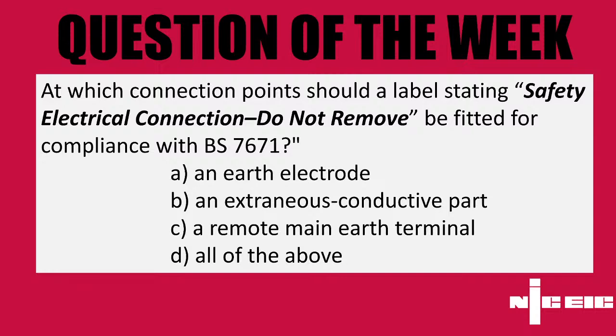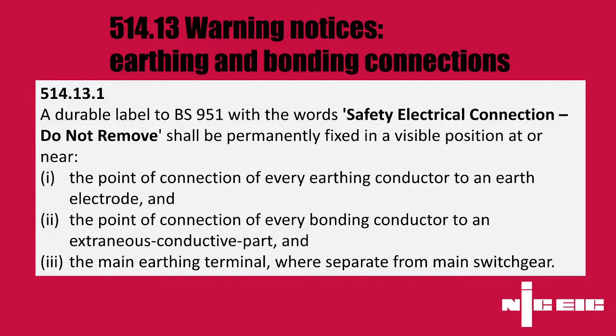If we actually go to that area of BS 7671, we'll see regulation 514.13.1, and that clearly states a durable label to BS 951 with the words "safety electrical connection, do not remove" shall be permanently fixed in a visible position at or near the point of connection of every earthing conductor to an earth electrode, the point of connection of every bonding conductor to an extraneous conductive part, and the main earthing terminal where separate from main switchgear. And it's probably that last one.